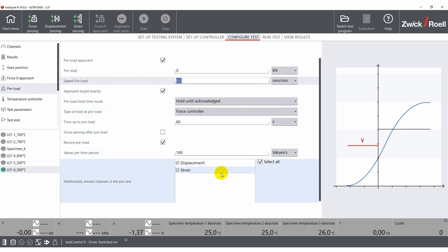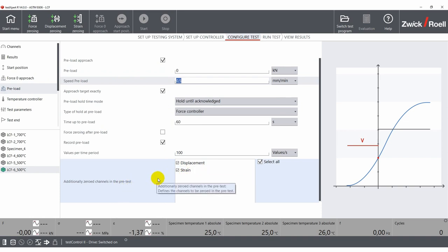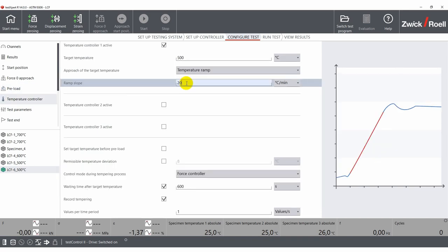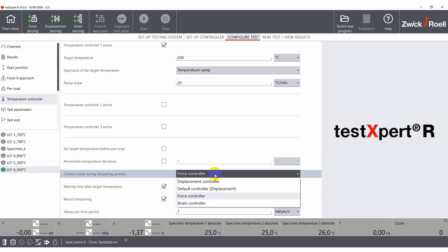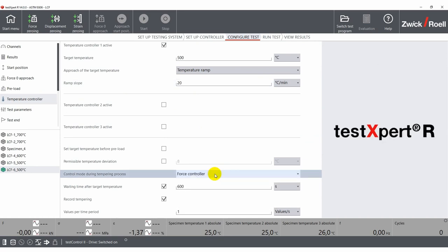If you are using a temperature chamber or high temperature furnace, the next step would be to set a target temperature and a heating ramp. The software also allows you to configure the control mode during the heating process. This is very important to assure that no stress is applied on the specimen due to thermal expansion.